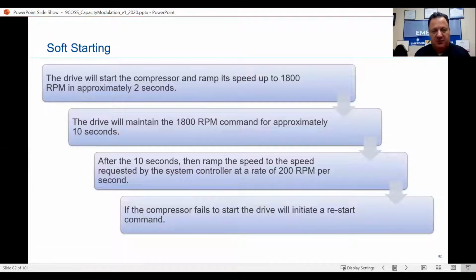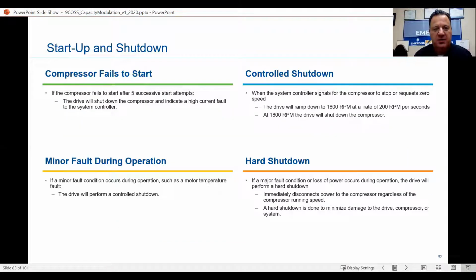Soft starting. The drive will start the compressor and ramp its speed up to 1800 RPMs in approximately 2 seconds. The drive will maintain that 1800 RPM command for approximately 10 seconds. After 10 seconds, it will then ramp the speed to the speed requested by the system controller at a rate of 200 RPMs per second. If the compressor fails to start, the drive will initiate a restart command. So let's go through these one by one.